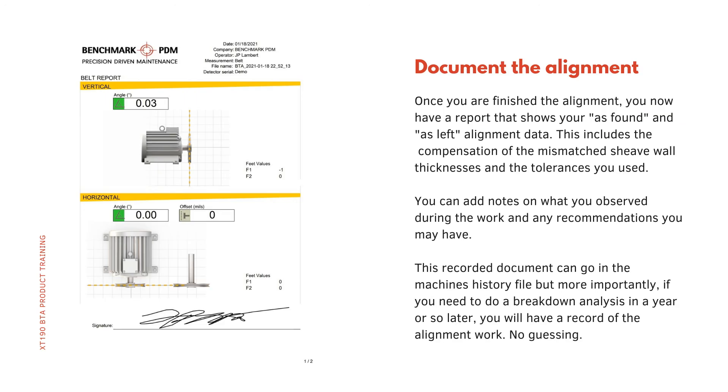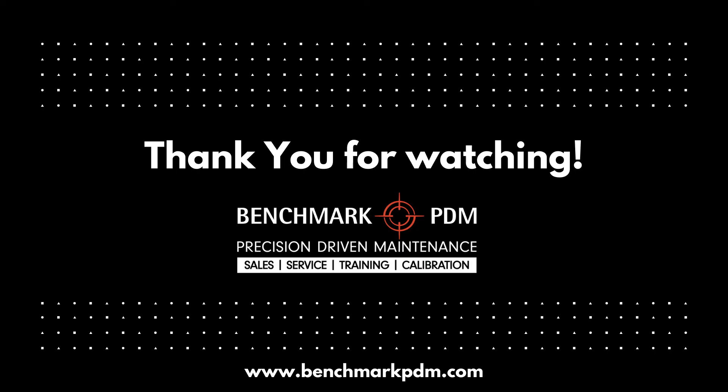Document the alignment: once you have finished the alignment, you have a report that shows your as-found and as-left alignment data. This includes the compensation of the mismatched sheave wall thicknesses and the tolerances you used. You can add notes on what you observe during the work and any recommendations you may have. This recorded document can go in the machine's history file, and if you need to do a breakdown analysis a year or so later, you will have a record of the alignment work — no guessing.